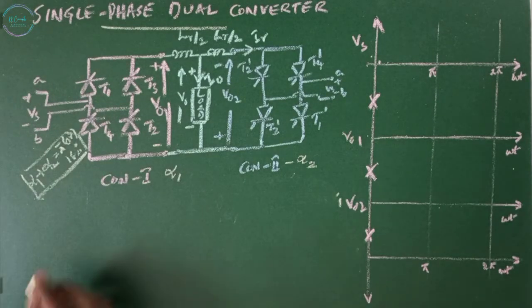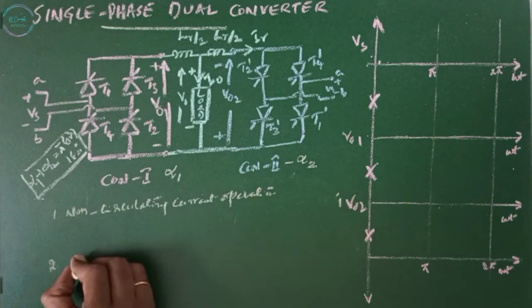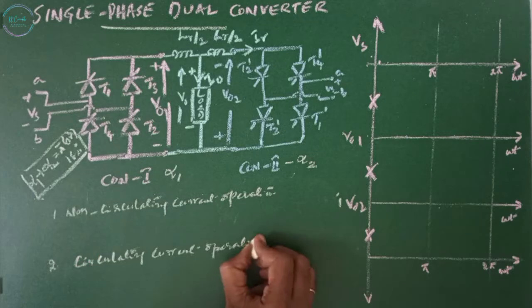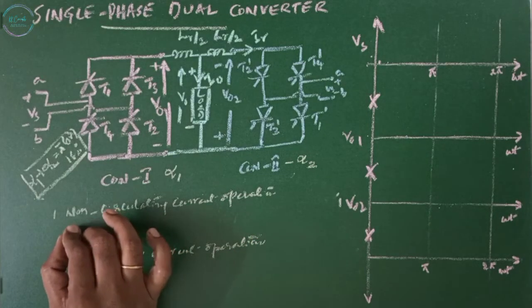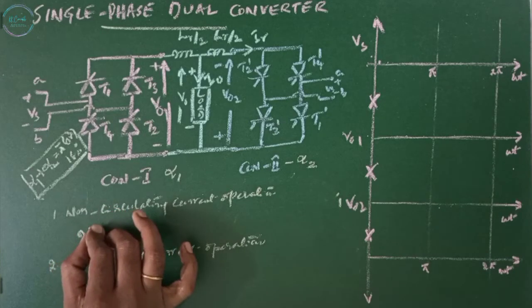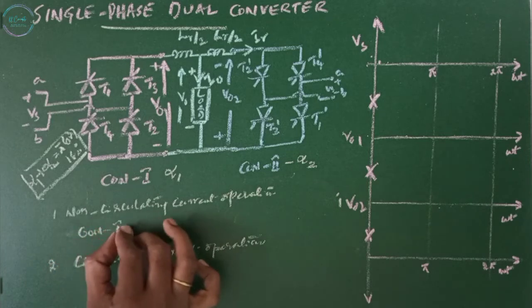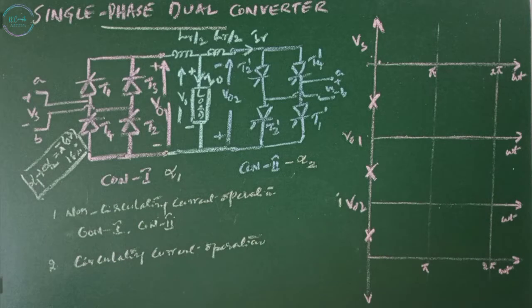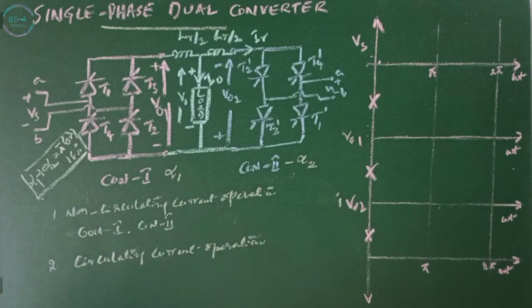There are two types of operations for a dual converter: non-circulating current operation and circulating current operation. In non-circulating current operation, at any instant of time only one converter is in operation. If converter one is in operation then converter two is in rest mode, and when converter two is in operation converter one is in rest mode. The switching from converter one to converter two is done by removing the firing signals to the respective converter. Here there is no problem of circulating current.